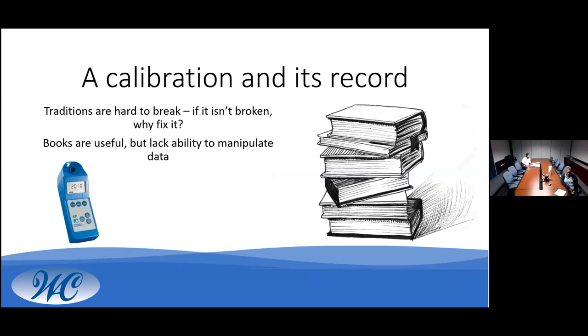So when you calibrate, you need to make a record. And the saying goes, if it isn't broken, why fix it? Well, writing has been a standard way of recording data for centuries. When our instruments were calibrated by one of our analysts, before even beginning to work with the instrument, a book had to be ruled up. Comments about the condition of the instrument, battery changes, sensor changes, along with the post-calibration readings were written down. This takes time, and to make matters worse, books don't come with a search bar.